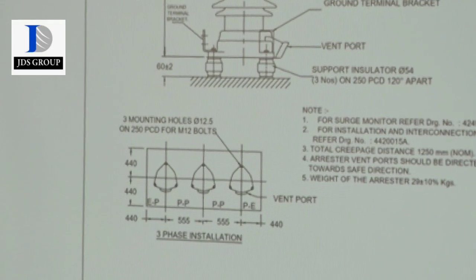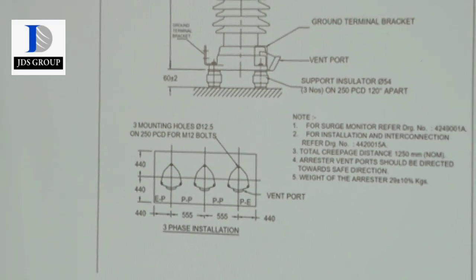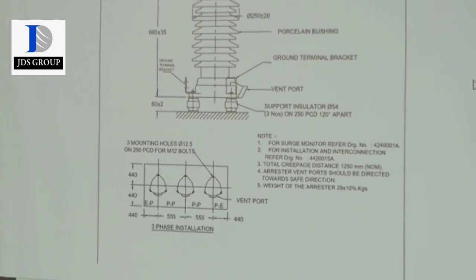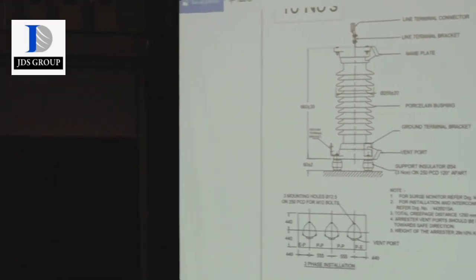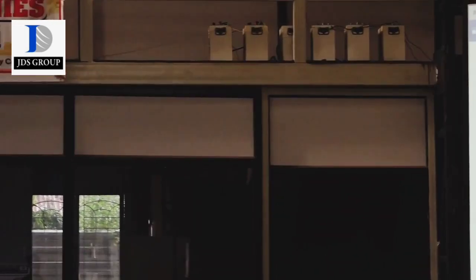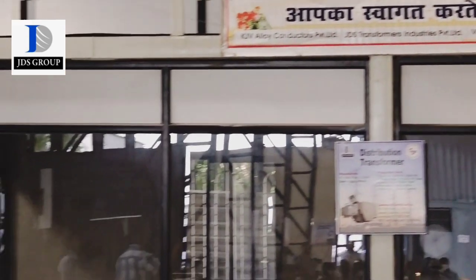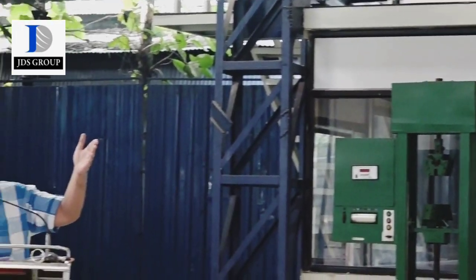When we are connecting between the line and earth, there is a specified voltage, and that voltage is to be taken care of. For an 11 kV system, one has to specify the voltage. Maybe for single line to ground it is 6.9. The line to line voltage is 11 kV between the two lines. Similarly for a 33 kV system. But the arrestor will use 9 kV for 11 kV and for a 33 kV system a 30 kV arrestor will be used, because they are connecting between the line and the ground. So it starts functioning at MCOV.